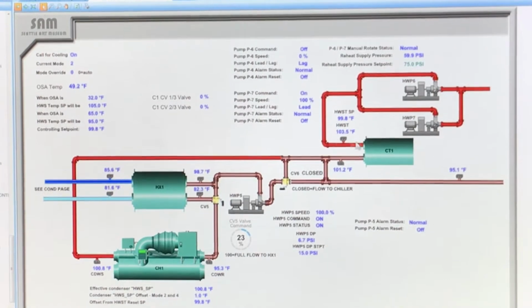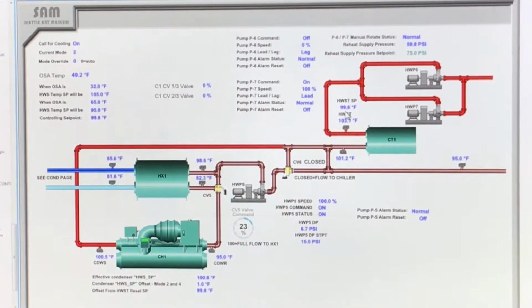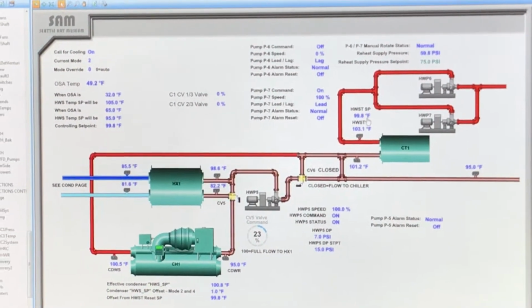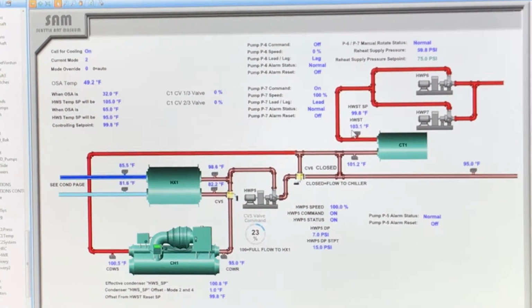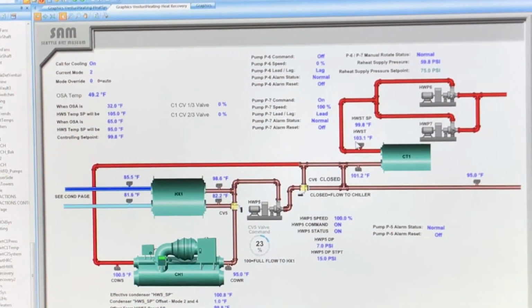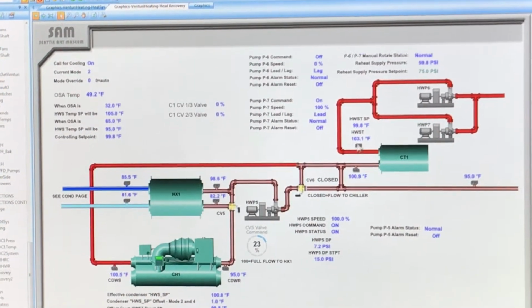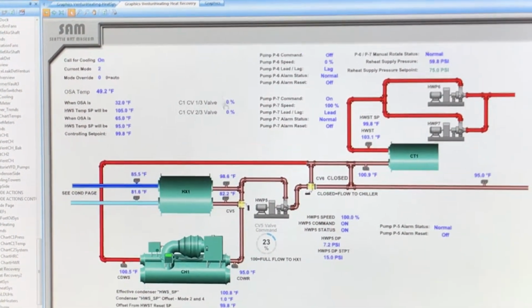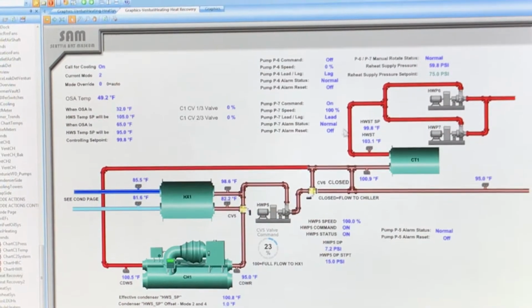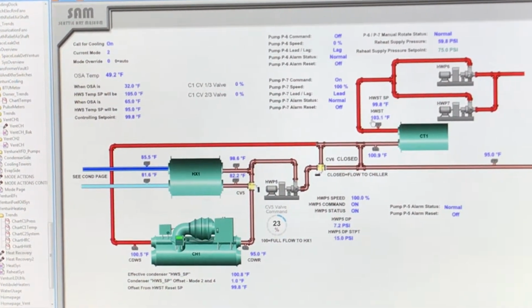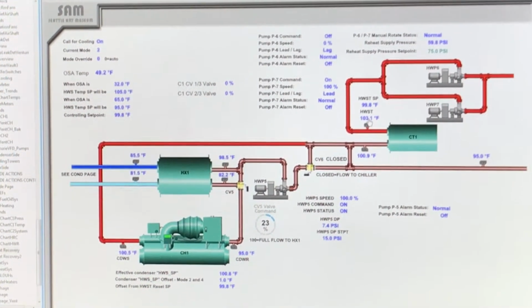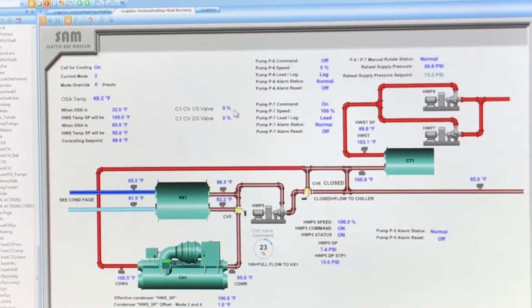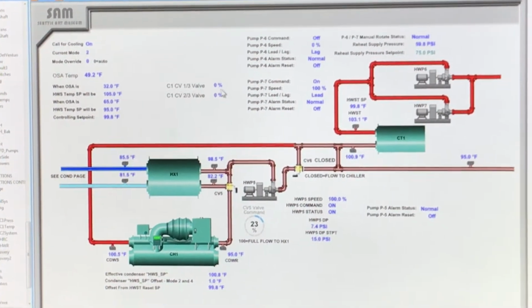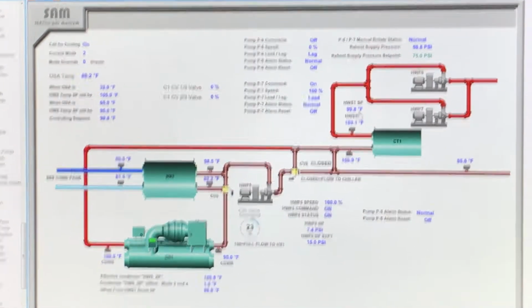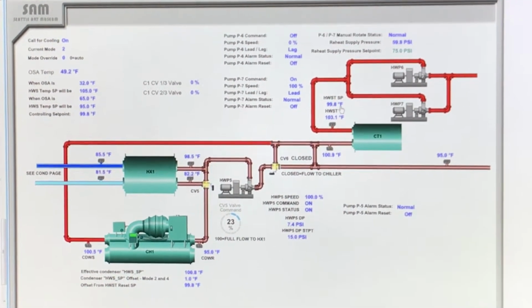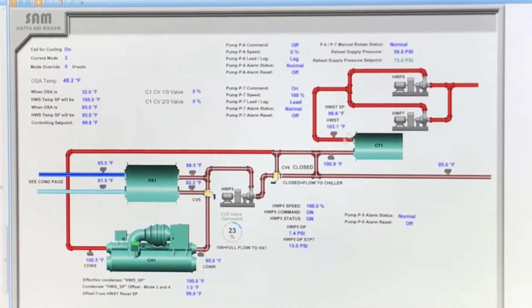Well, let's take a look at that. Good idea. The set point is what? 99.8. Our temperature is 103. So it doesn't need any steam to get to set point, so the steam valves are closed. That's where your saving is, exactly. So if this were to drop below 99.8, then these things would start to creep open and give you some steam. Okay. So the other question is, how come we're getting all this hot water?